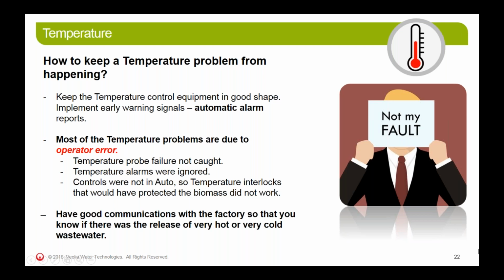Again, most of the problems, if there was a temperature problem, it would be, I keep calling it operator error, but it's not just the operator, it's failure to maintain equipment. It's not maintaining the probes, ignoring alarms, or not having the system control in auto. And again, that could be an accident. Somebody was working on something and put some controls in manual to test something and then forgot to put it back in auto. Check every night before you go home: is everything in auto that's supposed to be in auto?